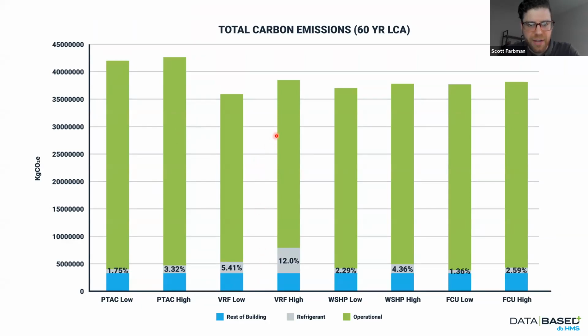On our VRF, we've got some variability here. On the low end, the total emissions for the VRF is the highest performing. So let's assume the best leakage rate possible. It's going to be the best performer across the board. Now let's look at VRF on the high end. Let's assume the worst leakage rate scenario possible. It is the worst performer of these three. And I'm just going to ignore PTAC for now because it's not something we typically push nowadays. We're really looking at VRF, a water source heat pump, or a 2 or 4 pipe fan coil unit system.